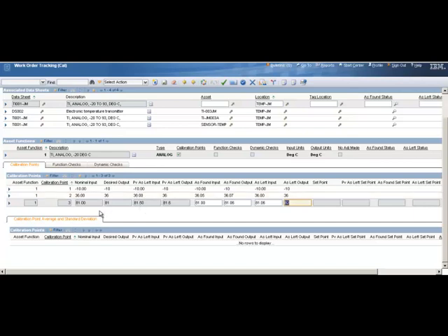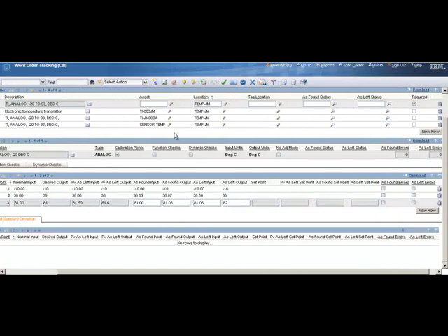And I may have to calibrate that by increasing my input signal to the right point and making sure that set point goes off. That would be discrete. And when you set your data sheet up, you'll set them up as function 2 might be discrete checks. Okay, and you have 1 or 2, however many calibration points there are. In this case, I kept it simple. They're all good readings. So now I'm going to click on the Save button to save this record. So go to the very top, click on my old floppy disk.